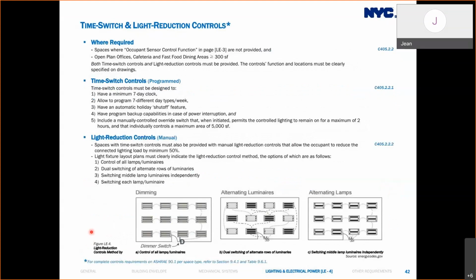Page LE4 focuses on time switch and light reduction controls, where they are required and what specific functions must be programmed into the time switch controls. And light reduction controls are often called bi-level lighting controls. And there are 4 different ways of fulfilling light reduction controls, as we illustrated on this page. So the first option is to make all lights dimmable here, and then connect them to a dimmer here. And then the second and third options are alternating fixtures or lamps, and grouping them into 2 separate circuits and dual switches, so that you could reduce the lighting level of the room evenly. And the last option is just switching each lamp and luminaire. Then it will be more than bi-level lighting controls.